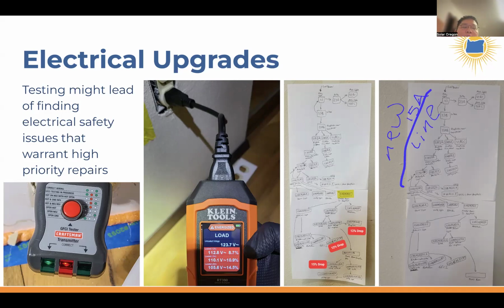Some other things were found, such as reversed neutral and hot wire runs. That happened to be a dishwasher plug, so it was out of sight and therefore inaccessible and not tested during the home's original electrical inspection many years ago. But we found it by pulling the dishwasher out to air seal around its perimeter, on an exterior wall, and decided to test that receptacle. Lo and behold, it was not wired correctly.